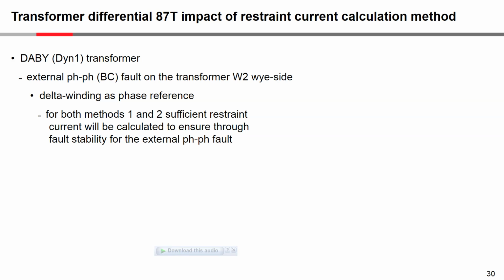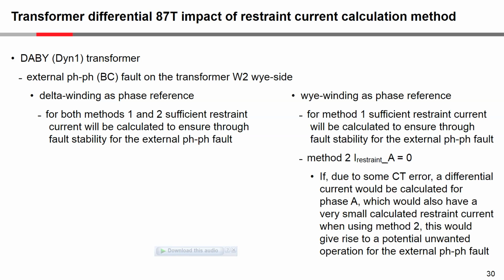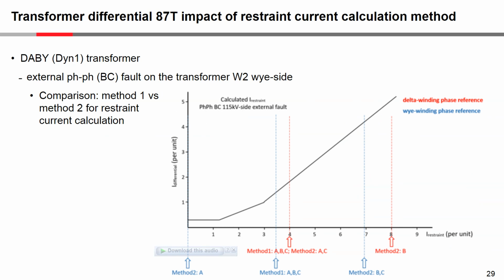If we look at the Y winding as the phase reference, so if we go back here and see, if we are using method 1, you'll see where the restraint current ABC is plotted. The curve is already into the second slope at this particular location. So again, for some small amount of error, we would have sufficient restraint such that we would get stability.